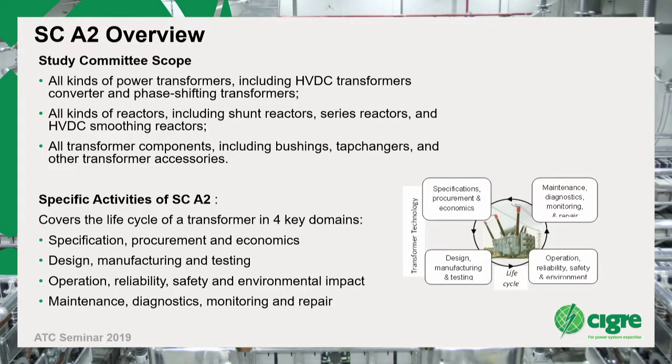The transformer category, power transformers, is mainly generator step-up transformers, then transmission transformers used for stepping up and stepping down, and step-down transformers used in distribution networks. It also goes into the industrial sector, with power transformers doing functions like smelters and furnace transformers, then HVDC transformers, going into the DC space. From the last presentation, it seems we have the potential to make 10 gigawatts of HVDC transformers in future for the Singapore link. That's good. And then phase shifting transformers, connecting different power systems. These could be large, close to 2,500 MVA, 3,000 MVA. In the Australian network, we have some, but not of that larger capacity.